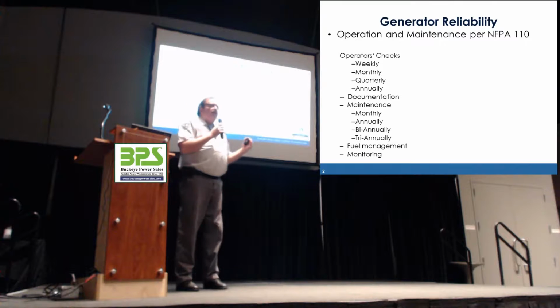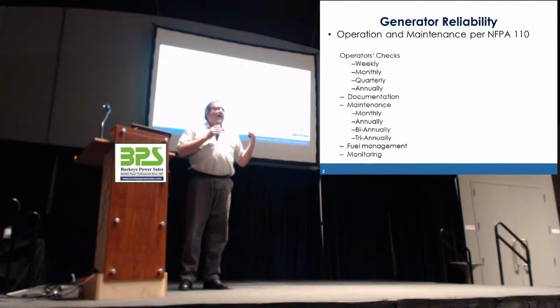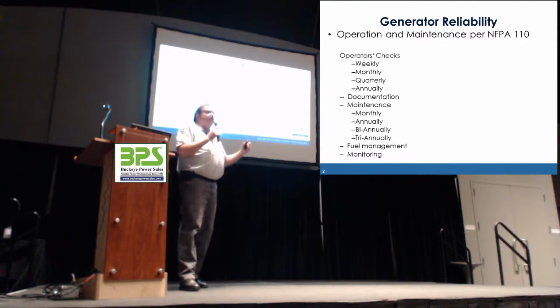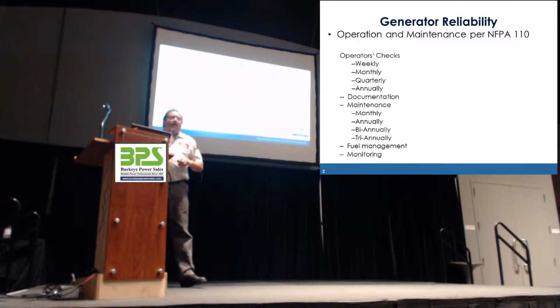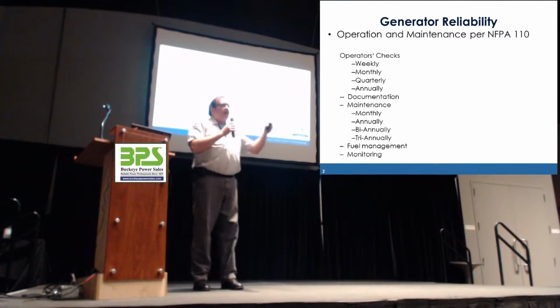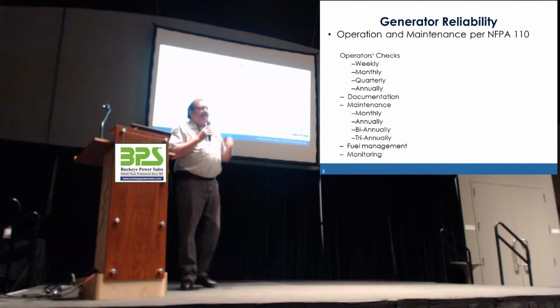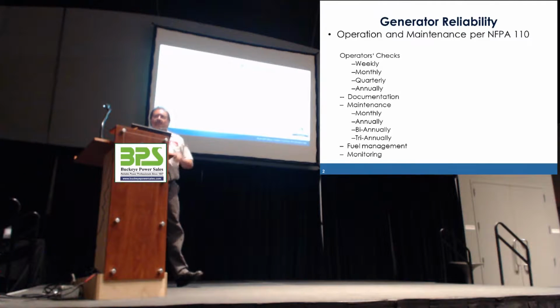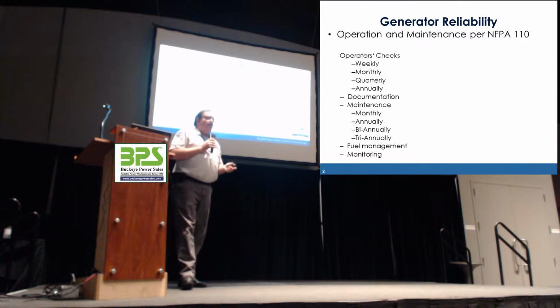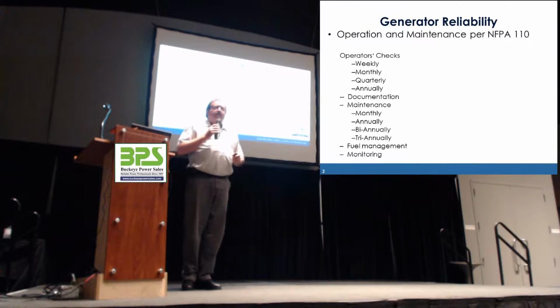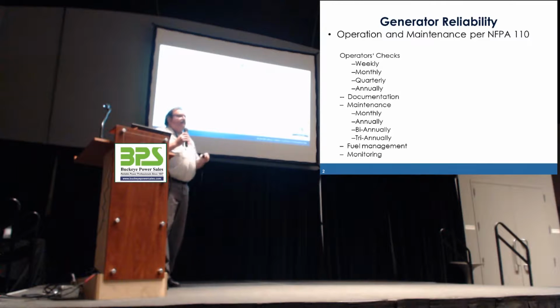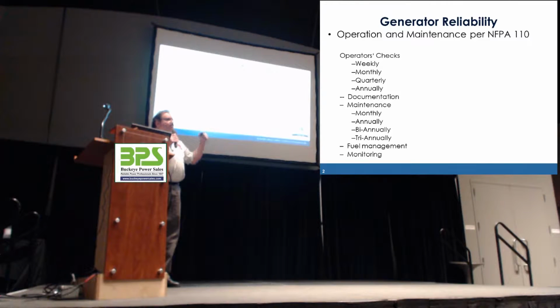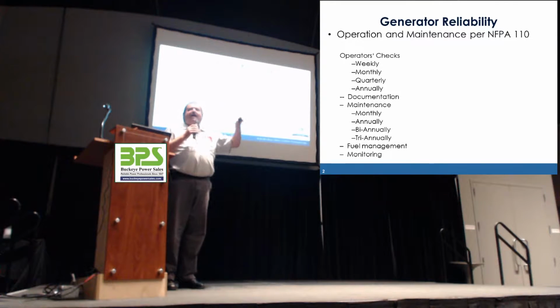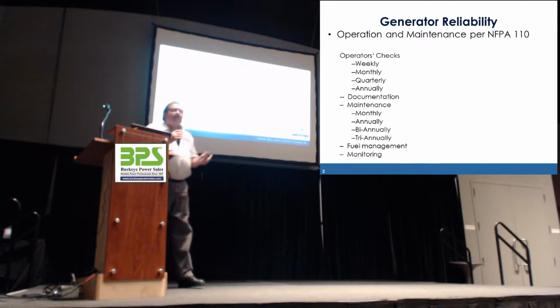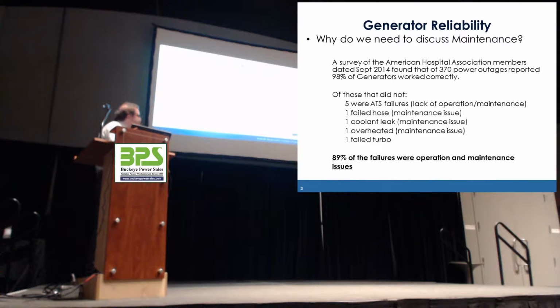So we take NFPA 110, which is our highest standard that we have, and we're going to discuss things in there. In the code, there are things that it says you shall do, and shall means it is to be done. Should is also in there, and of course should, we all know, means that it's a recommendation, but they're not going to hold you to it. If you want to strive for that uptime, the way that we're going to do that is take all of the shalls and all of the shoulds to try to alleviate that risk.